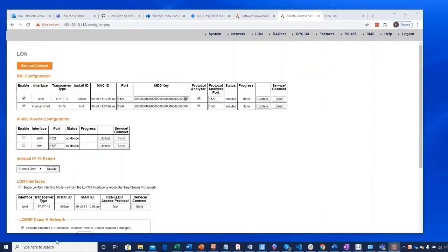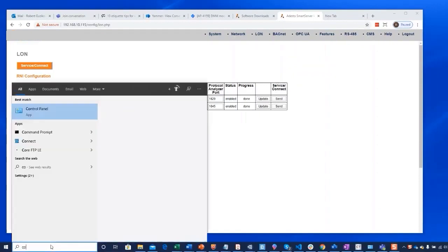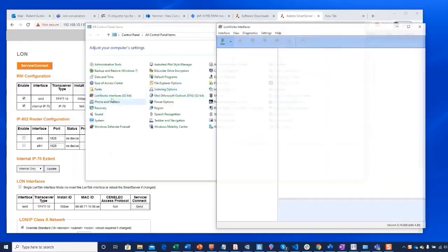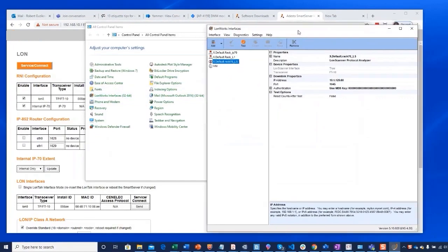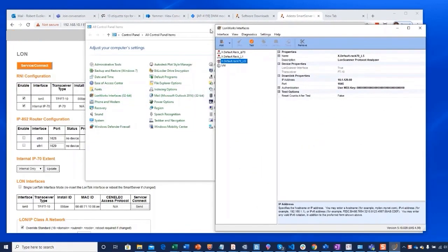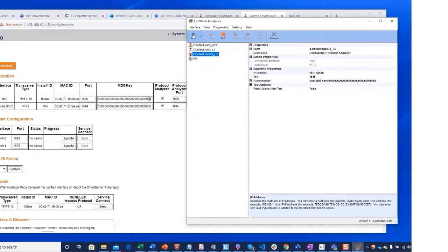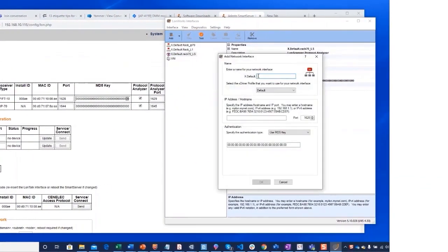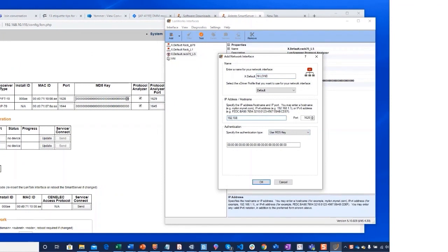On your PC, access the Windows Control Panel and launch the LonWorks Interfaces 32 applet. Select and add the type of RNI you want to create. Name the RNI that is something memorable to you. For the IP address, use the named IP address if DHCP and DNS server exists. This is not the case in this particular network, so a four decimal dotted address is used. The port is set to match the corresponding interface in the configuration UI.